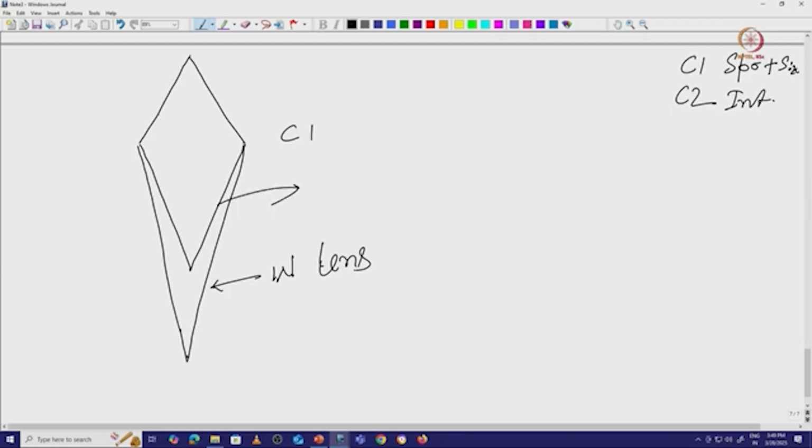So here you can see the electrons are coming and merging at one particular point, and this is my C1 lens current. If I use a comparatively lower C1 lens current, what will happen? The electron beam will converge at one particular point. This is called the weak lens, which we already discussed as the weak C1 lens. We can say this is a comparatively intermediate condition.